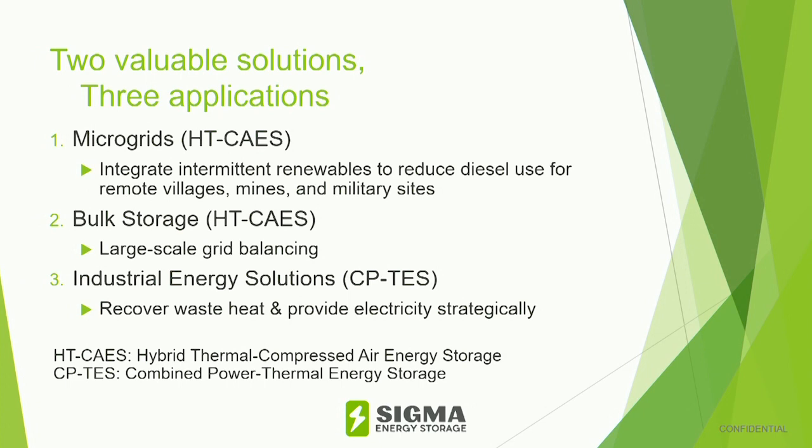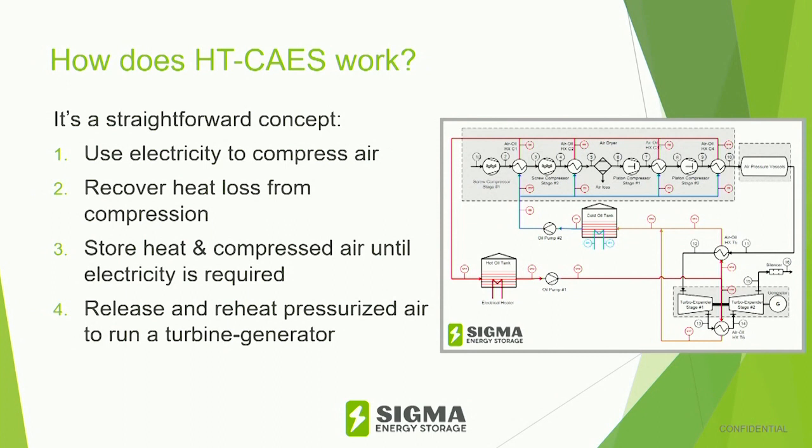Just to give you a brief explanation of what it does, it's a straightforward concept. Whenever energy is available from the grid, we start a group of compressors, small or very large, at which time we compress air that can be stored. In a small size system, we store the compressed air in storage vessels, above ground cylinders that can be deployed anywhere. At large scale, we use the same process, but we store the compressed air in subsurface reservoirs, either salt caverns or porous rock formations that have sizes that are measured in billion cubic feet, massive size.